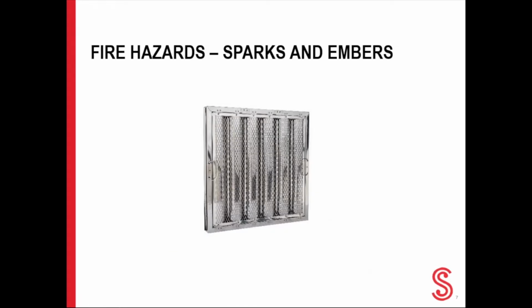So how do we reduce creosote fires? Well, as you know, solid fuel cooking appliances produce spark and embers, some of which may travel upwards into the hood system. When using solid fuel appliances, spark arresting baffle filters are required. Spark arresters have a special system that catches the spark or ember before they enter the baffle filter and the ductwork. Failure to have spark arresting filters can result in a fire as the spark or ember land on grease and other products in the baffle filter or ductwork.